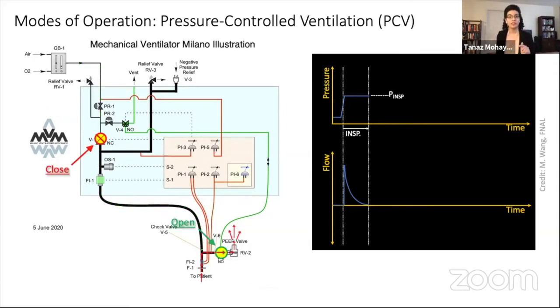When the ventilator reaches the end of the inspiratory phase, the expiratory valve at the bottom, now shown in green, opens. Because there is positive pressure in the patient's lungs, the air flows out of the lungs and vents out through the PEEP valve at the bottom. Meanwhile, the incoming airflow valve, now in red, closes in order to prevent any more flow of medical air to the patient.